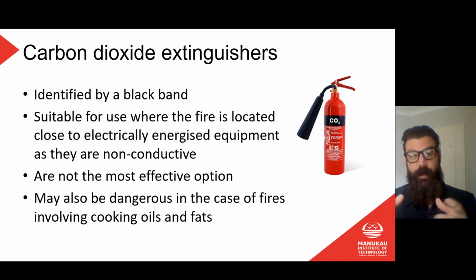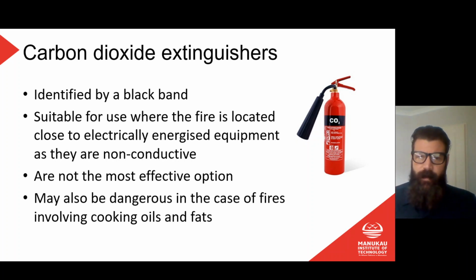But if it doesn't put it out and then you stop, then that fire is going to come back again because the CO2 will slowly dissipate, although maybe not immediately. And if you think about that, spraying that CO2 and it going everywhere, you probably realise what some of the other hazards are. One of those is going to be the fact that, particularly in a smaller enclosed space like a switchboard room, for example, if you wandered into a switchboard fire in a big building with a switchboard room, and you start spraying that CO2 around, not only will the fire be deprived of oxygen, you might be deprived of oxygen as well, which is not going to be a good look. So we don't, because then the fire probably won't go out and you'll fall over dead, and then you'll get crispy fried while you're having a nice nap on the floor. So we just need to be aware of that hazard as well.